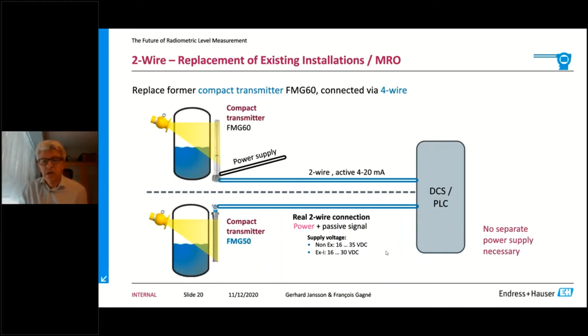We can also look at other applications where there was maybe a separate transmitter used, which would require a 4-20 milliampere output but would also require an additional power supply, and then there was this connection to the detector itself. In most cases, if we now replace this with a loop-powered instrument, this cable would probably be at least 2 wires, maybe 3 or even more. In the absolute majority of cases, these can be reused if so wished, and then you'd just extend it over to the 4-20 milliampere output from that remote transmitter and then into the PLC or the DCS.